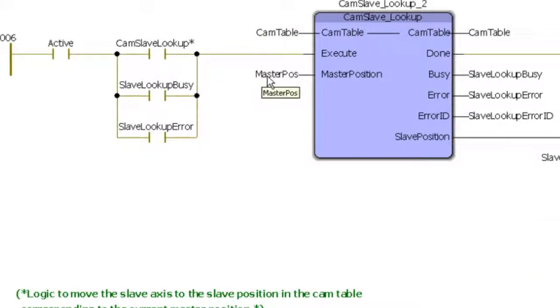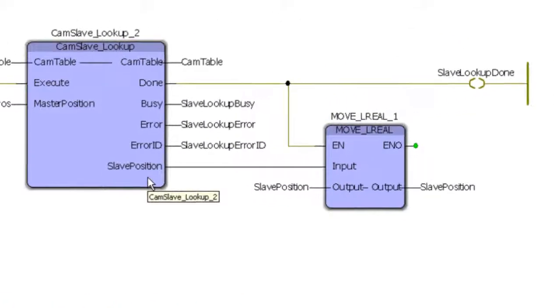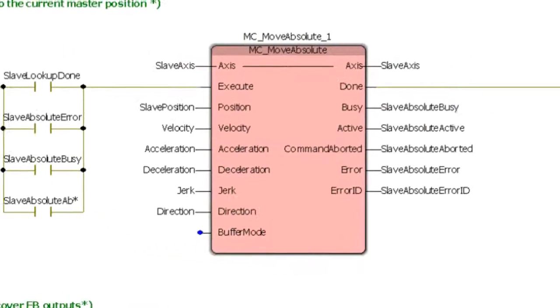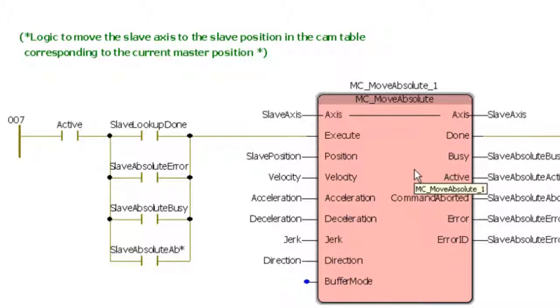Then given the master position, it's going to have the slave position fed back to it, at which point it will then do an absolute move and move the slave position into its correct position. So that the cam will be back in synchronization once we do another cam in function block.